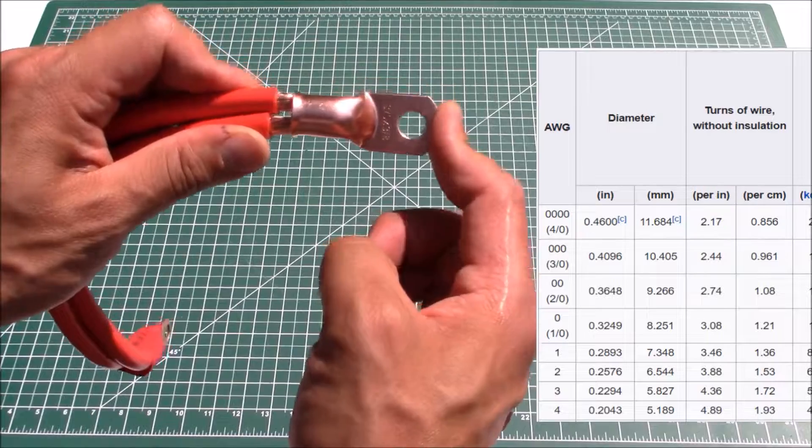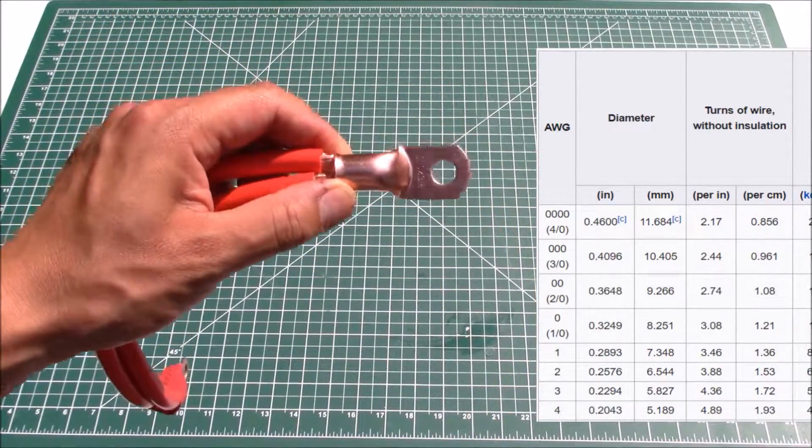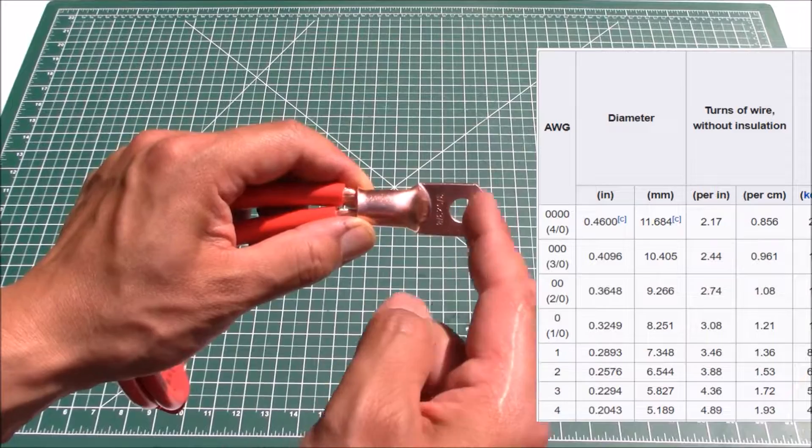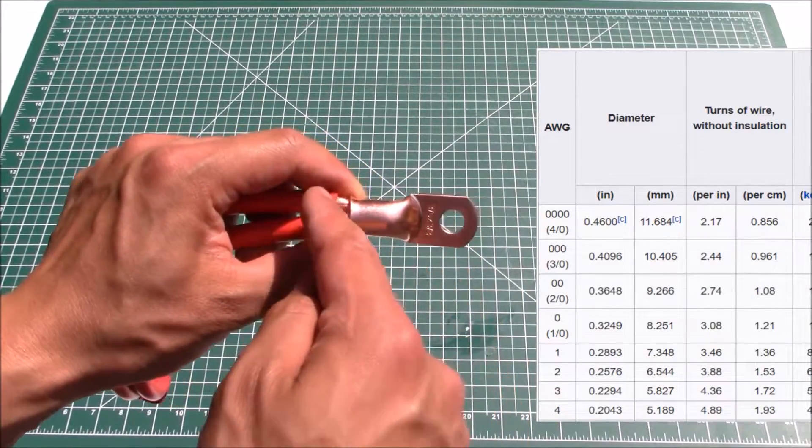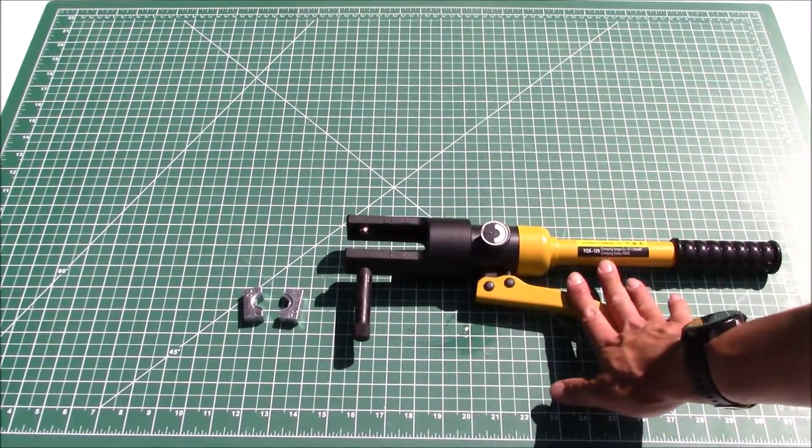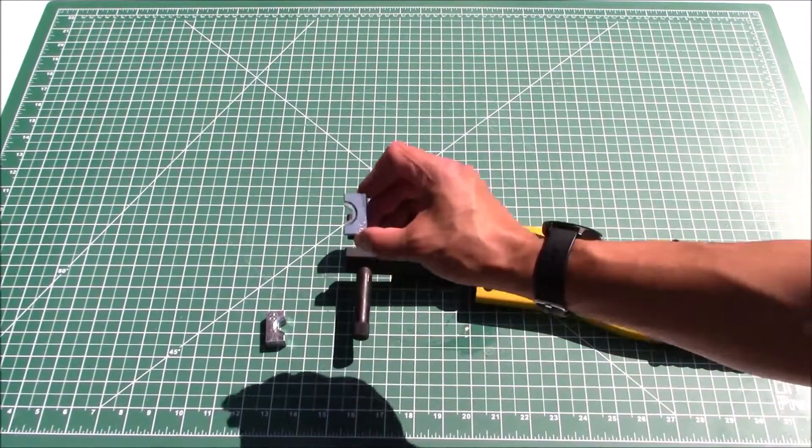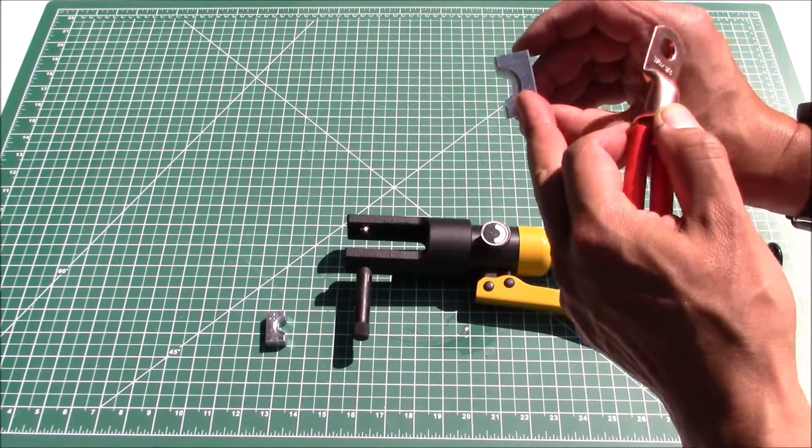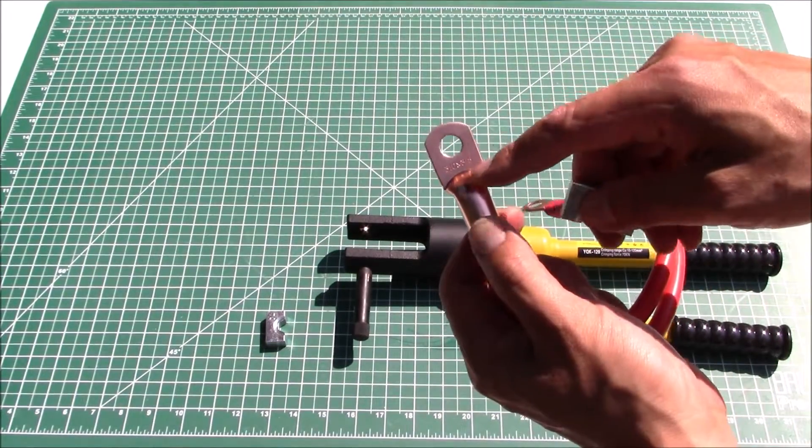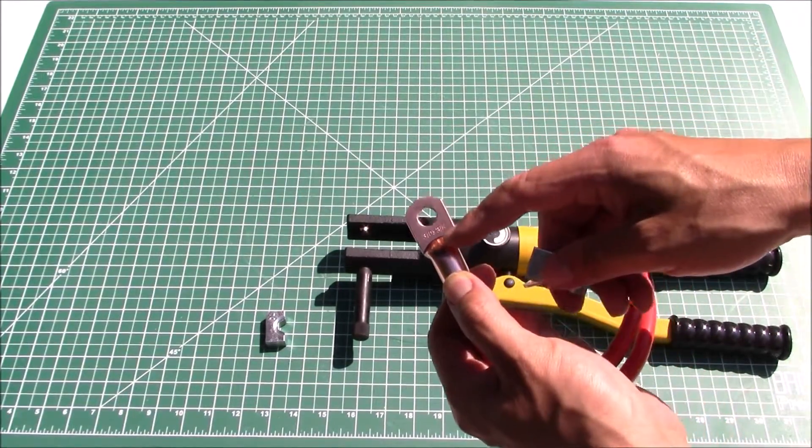Now that we've got the wire all set, let's go ahead and get the crimping tool so we can actually first crimp this lug or this ring terminal onto the wire. I've got the crimping tool here and I've got the appropriate size dies. These crimping dies - you're going to want to make sure that the size of the crimping die matches the size of the lug or the terminal that you're trying to match.